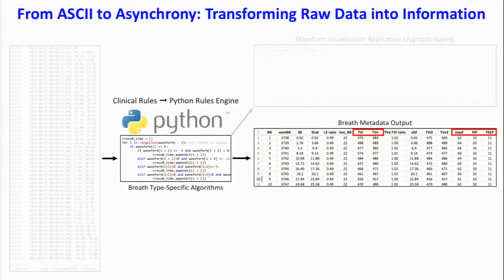And then we have a series of matrices that produce output. One we call the breath metadata output. You can see breath number in the rows, and then things like the inspiratory and expiratory tidal volume, peak flow, peak pressures, and PEEP. All of these we can reverse compute from the raw waveform data themselves.